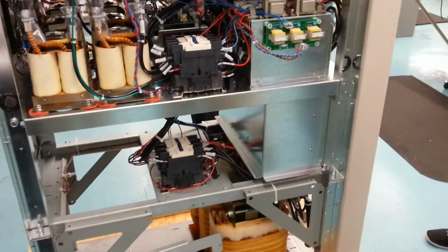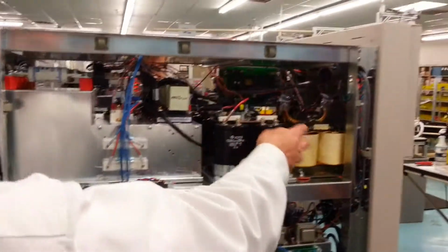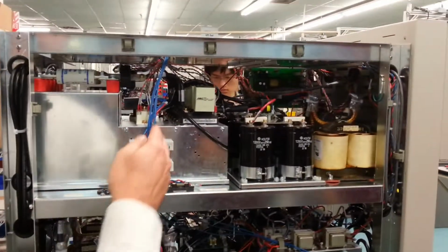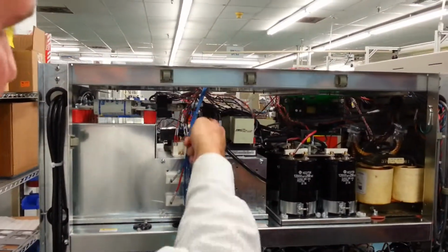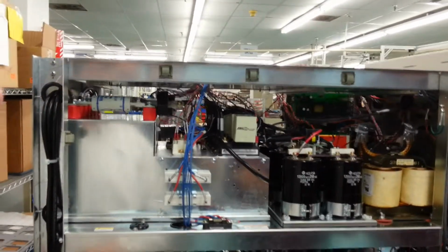Right. And then we got one, if you want to take a closer look at this one, you can. This is that 4200, just like those over there, but a finished one. One transformer in this case, isolation, bypass circuits, a dual input, same thing. Here's your L circuit here. Control, contactors, same thing, input, output, DC bus, DC chopper, DC cap. And then across here are all your IGBTs, input and output chopper. So this is a dual conversion unit.